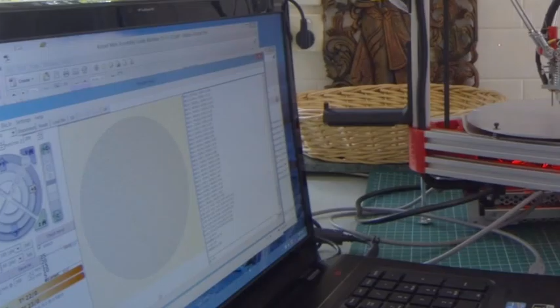So remember those measurements we had? What you have to do is get it so that when it comes back to the correct position, it is at the right height. You have to change that. But before we move on to that, here is the recording, the data logging of the bed position and their height. Then it subtracts differences. And it shows you what it is. Now, you'll need to do several probes before you get this right. And all I did is just open up a normal notepad and I called it probe test results and the date. With anything in this column, you can just highlight it, drag and copy and paste, which I did. So I put it in, down the bottom, I worked out the difference. And the range was minus 1.21 millimetre to minus 0.6, a difference of 0.61 millimetre on the table.